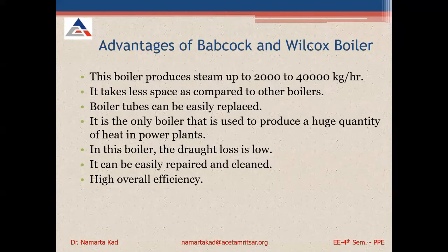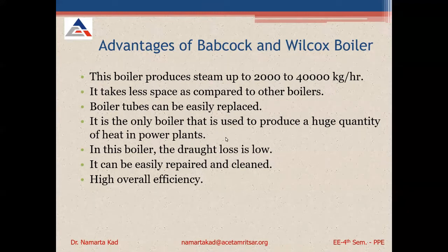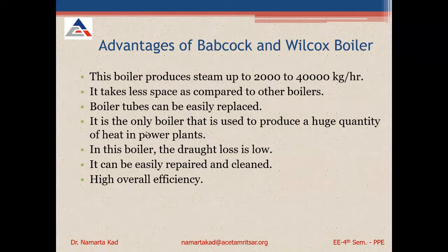Advantages of the Babcock Wilcox boiler: it produces steam at 2,000 to 40,000 kg per hour, takes less space compared to other boilers, and the boiler tubes can be easily replaced. It is the preferred boiler for producing large quantities of steam in power plants. The heating area is more than in fire tube boilers, steam is generated more quickly, and the draught loss is low.